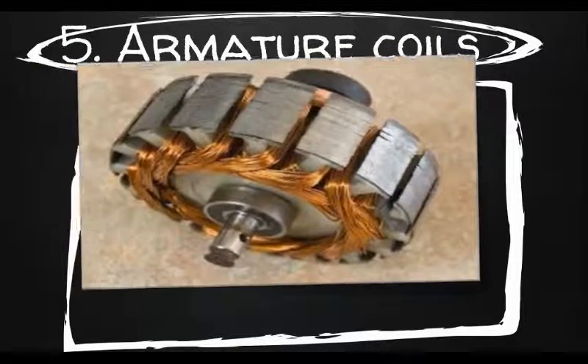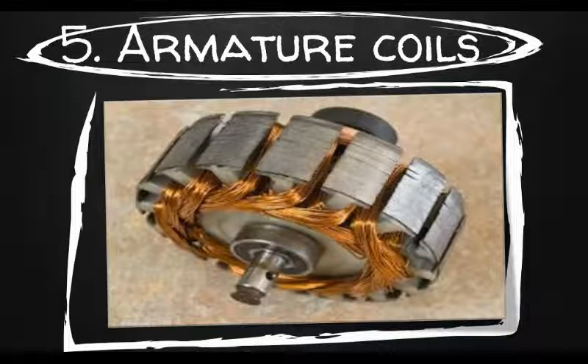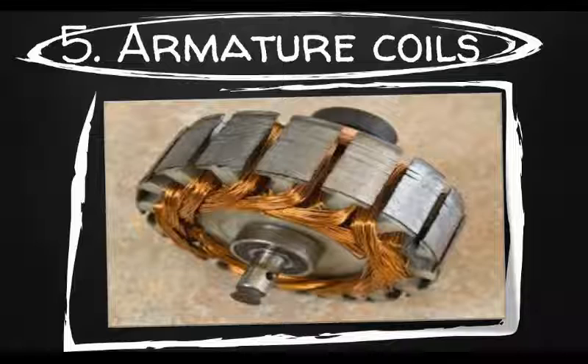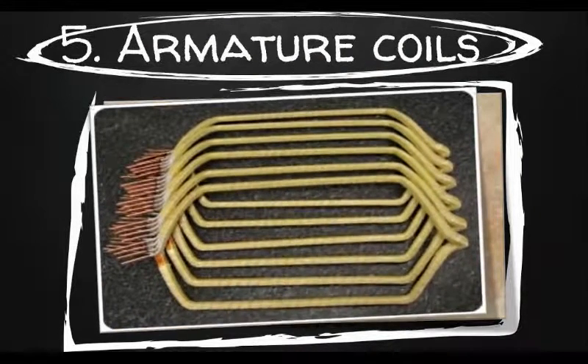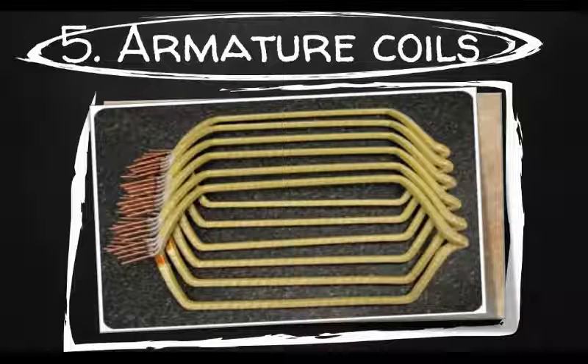Armature coils or armature windings: The armature windings are usually former wound. These are first wound in the form of flat rectangular coils and are pulled into their proper shape in a coil puller. Various conductors of the coils are insulated from each other. The conductors are placed in the armature slots which are lined with tough insulating material. Each coil consists of a number of turns of wire, each turn taped and insulated, and each side of the turn is called the conductor. There are two types of windings: lap winding and wave winding. The difference between the two is merely due to the different arrangement of the end connectors at the commutator end of the armature.